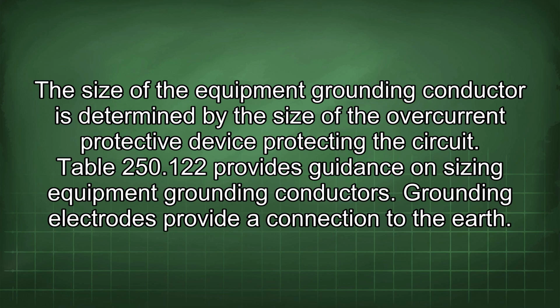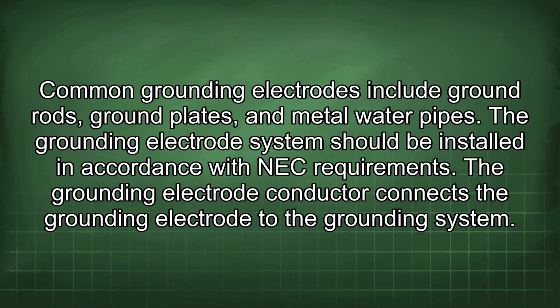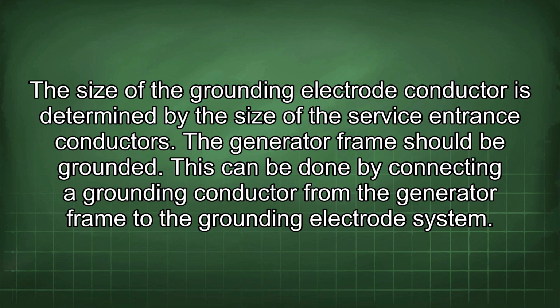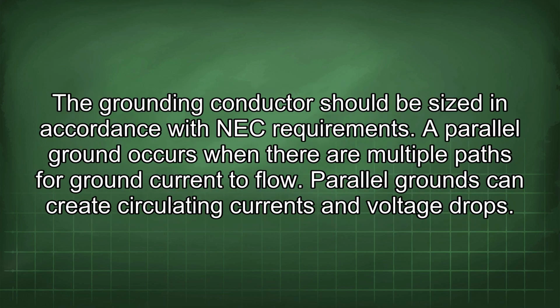Grounding electrodes provide a connection to the earth. Common grounding electrodes include ground rods, ground plates, and metal water pipes. The grounding electrode system should be installed in accordance with NEC requirements. The grounding electrode conductor connects the grounding electrode to the grounding system. The size of the grounding electrode conductor is determined by the size of the service entrance conductors. The generator frame should be grounded. This can be done by connecting a grounding conductor from the generator frame to the grounding electrode system. The grounding conductor should be sized in accordance with NEC requirements. A parallel ground occurs when there are multiple paths for ground current to flow.